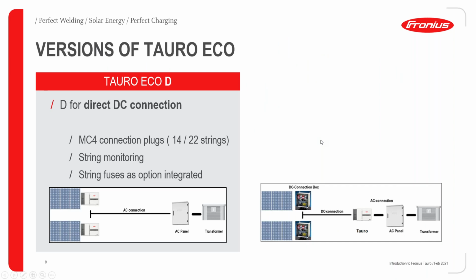So when you take a close look at the versions of the Tauro Eco inverter, as I mentioned, we have Tauro Eco D. D is for direct DC connection. This inverter is used for decentralized topology. That is, you want to place the inverter as close as possible to the panels. Yeah, and then you will bring a long AC cable to the AC panel and transformer. So in this Tauro Eco D version, you will have MC4 plugs at the bottom of the inverter. If it is 50 kilowatt, then 14 strings are possible. If it is 100, then it's 22 strings.